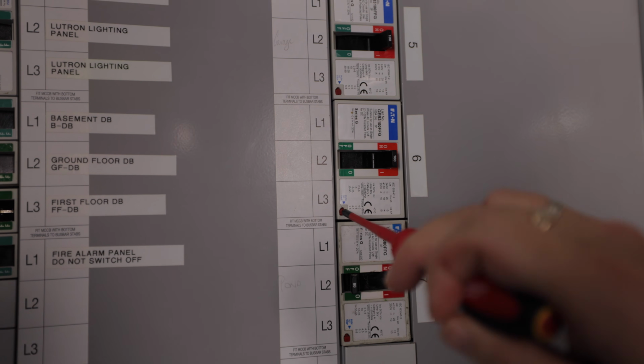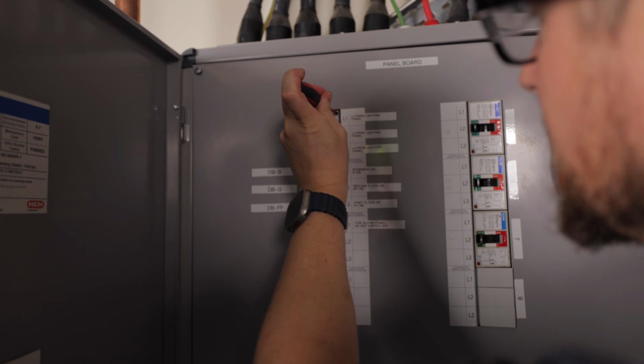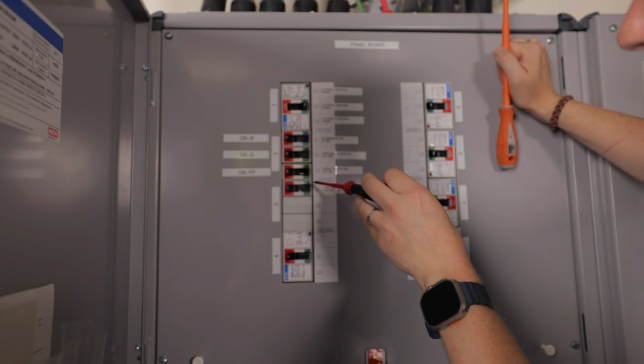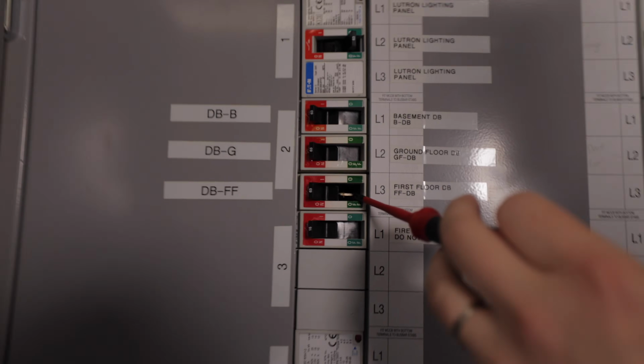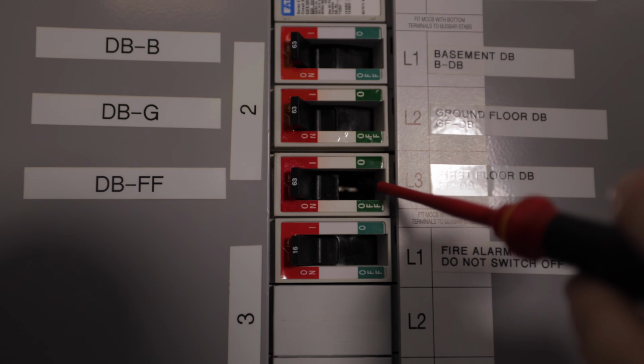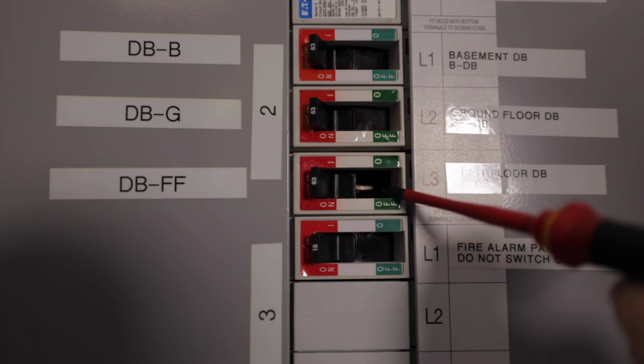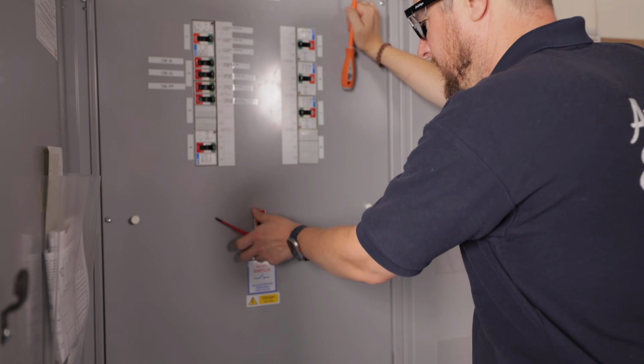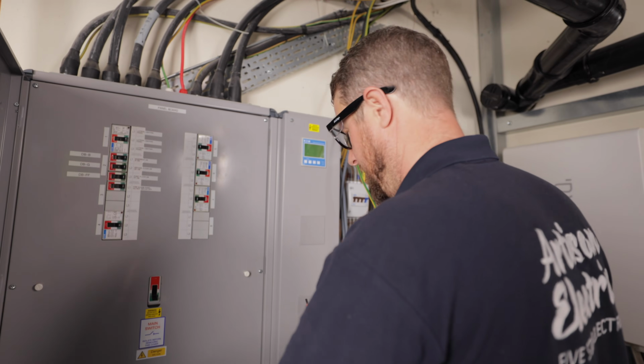It says press to trip, we trip. There you go, it goes off. Same with the plant room. There we go, that's this room. Oh, and that one looks like it's broken. You see, this is why it's good we check. There's a piece missing there. First floor DB, sort of like access to metal inside there. That goes off, and that should be all the power in this board off.